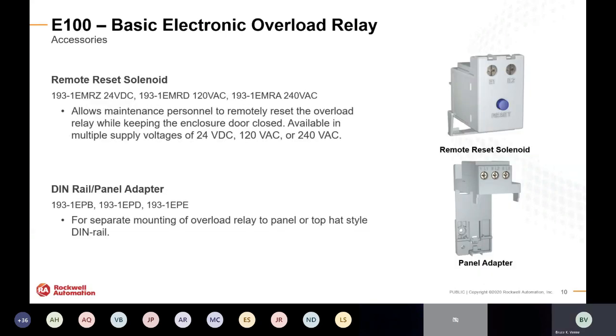The remote reset solenoid is an electromechanical component that fits on top of the overload, so that if you wish to remotely reset the overload relay, you can use it to do this. It comes in three different voltages: 24 volt DC coil, 120 volts AC, and 240 volts AC. You just apply power to this device, and that little blue button plunger activates and pushes the reset button for you, either in the panel or in an MCC, so you don't have to open the door to do so.